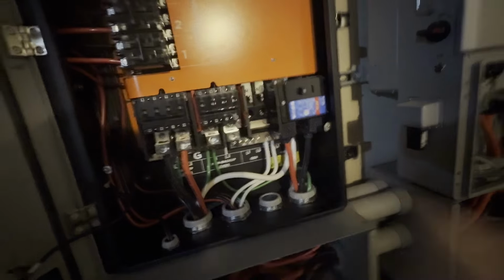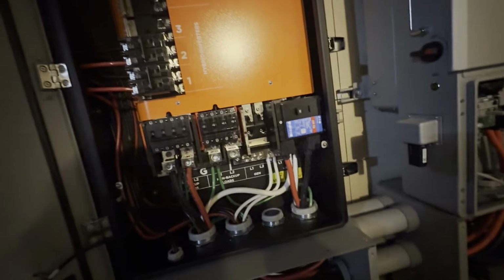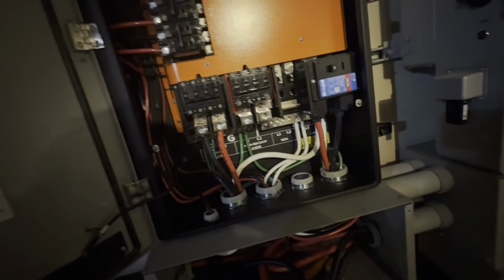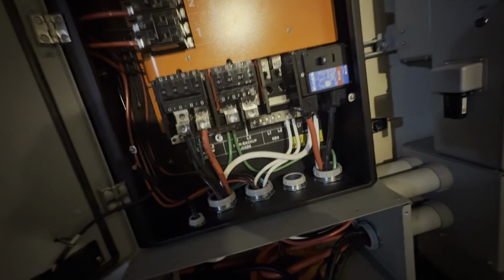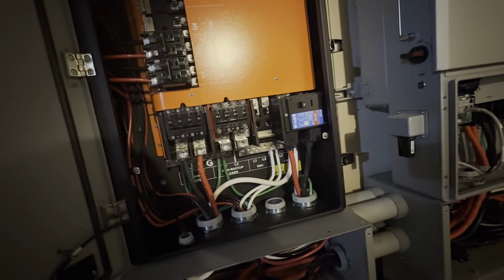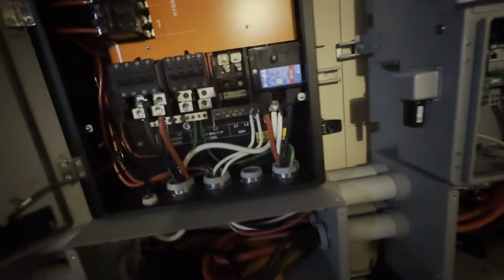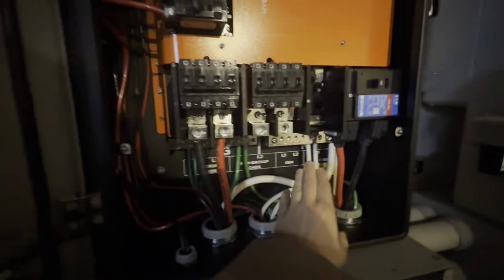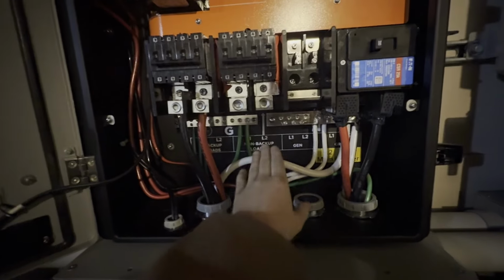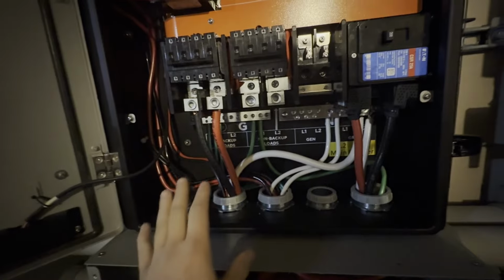It's not really necessary since I do have the breaker out there, but it just seemed like a thing to do. I don't know. I might be required by code to have it because this would then be the service disconnect, whereas outside is the emergency disconnect. I don't know. I just like having more options. But anyway, so we've got the neutral bus bar, we've got the ground bus bar. Again, not connected, right? Because there's only one place where we bond them, and that's back at the meter pedestal.